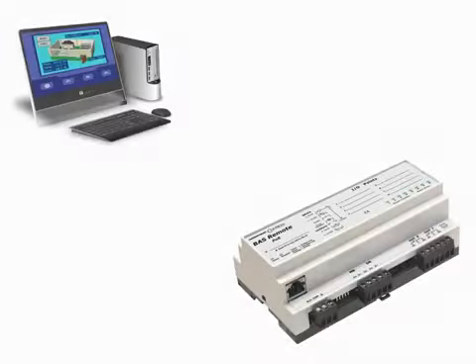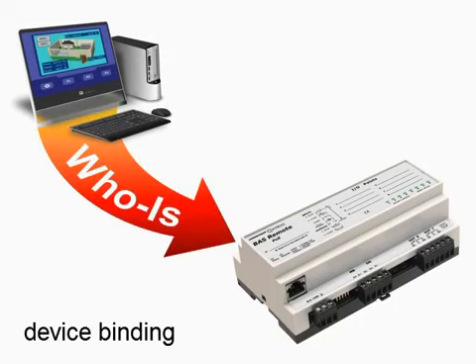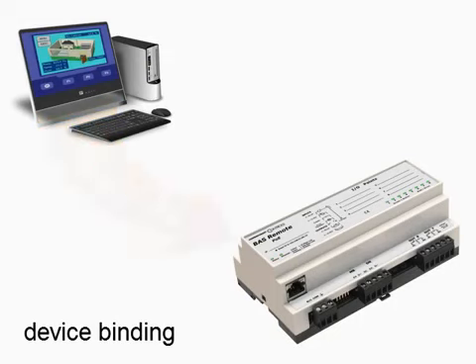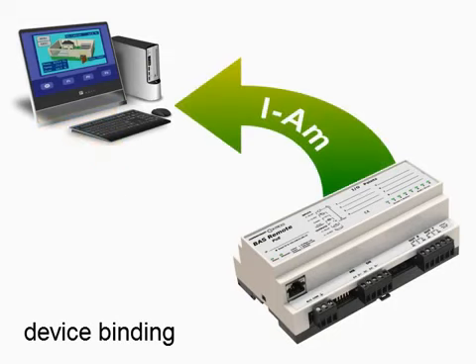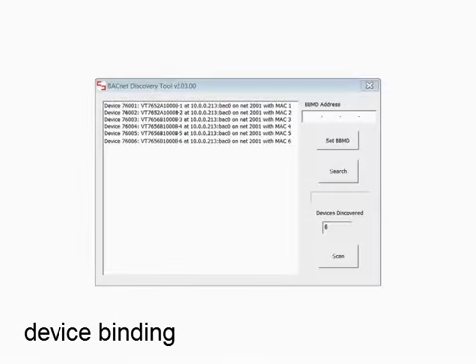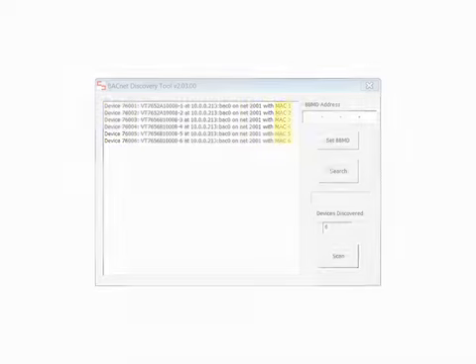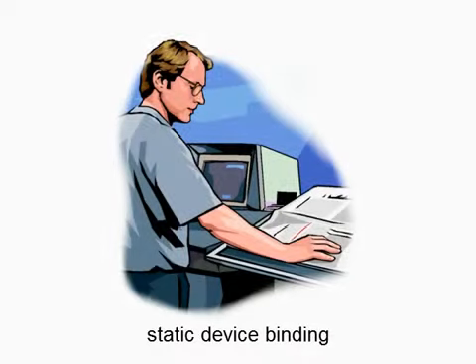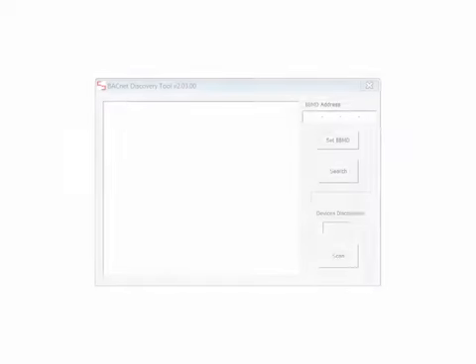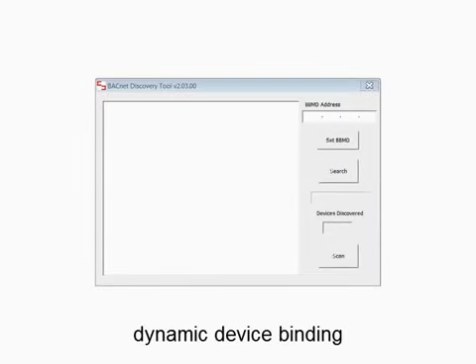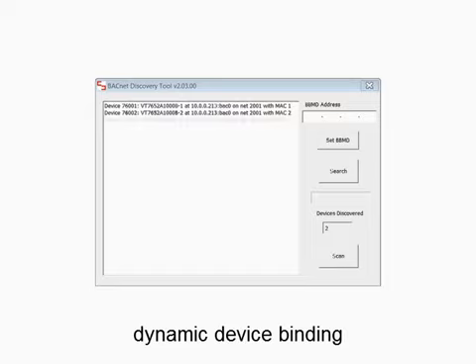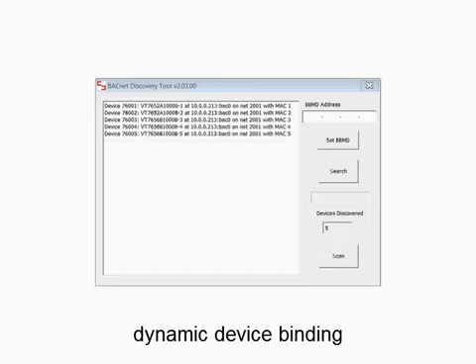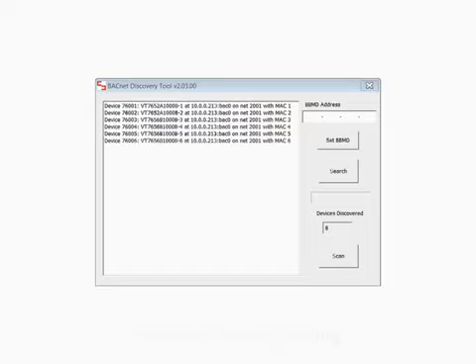Device binding is the process of establishing connections between devices by uniquely identifying devices using device instance, network number, and MAC address. Static device binding requires human intervention. Dynamic device binding is an automatic discovery process using Who-Is and I-Am services.